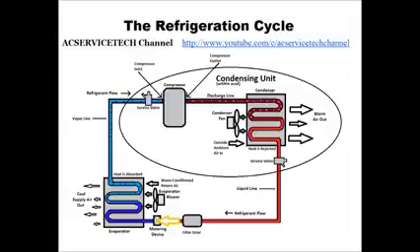So in this case, we have a high pressure, high temperature liquid refrigerant coming through and hitting the metering device. The metering device is only going to allow a small amount through. Then it turns into a low pressure, low temperature, 80% liquid, 20% flash gas mix, but it's mainly going to be a low temperature, low pressure liquid until it gets to the middle of the evaporator coil.